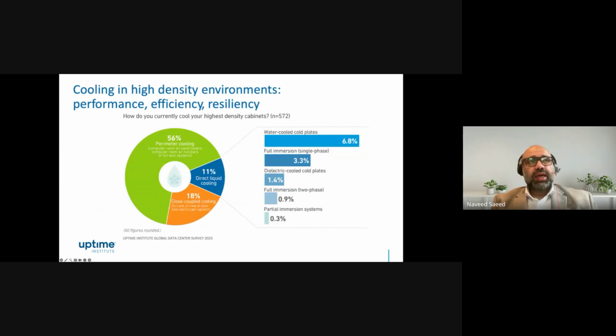If we look at today, this is Uptime Institute's Global Data Center Survey from 2023, which shows that 56% of facilities are still using perimeter cooling, with CRAC units or fan wall units, but it's some kind of perimeter cooling. 18% are using close-coupled cooling, that includes in-rack cooling, in-row or rear door heat exchangers, and 11% are using direct cooling, and that includes all kinds of direct-to-chip, DLC, and immersion cooling.